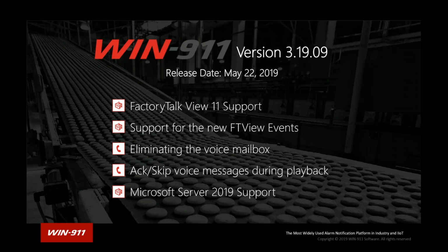What we noticed when we did our testing initially with FactoryTalk View 11 was that these events would come through our filter. We would alarm on them, great. But if you wanted to acknowledge it to stop the call outs, we try to send an acknowledgement back to FactoryTalk, and it doesn't acknowledge. So it never acknowledges. So on this next release, you'll have an option to say yes, I want to bring events into WIN-911, or not. That's at a global level.